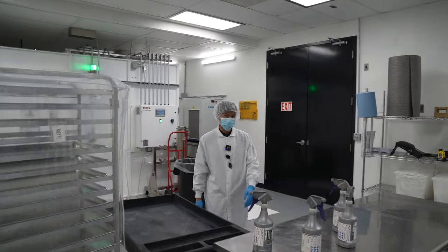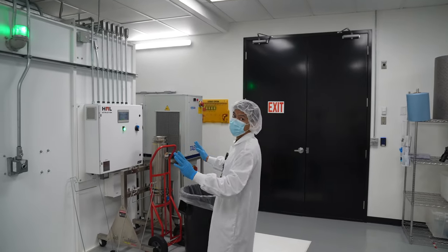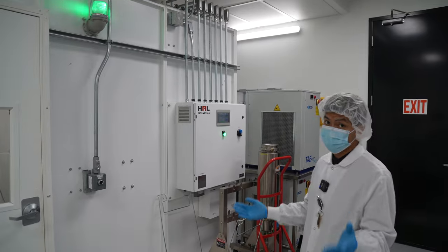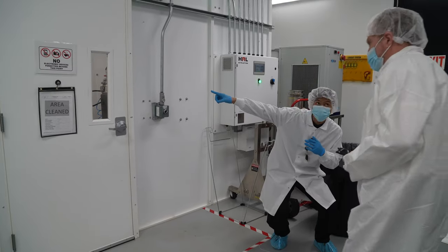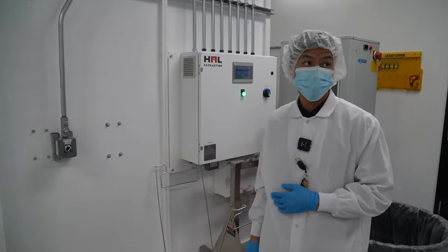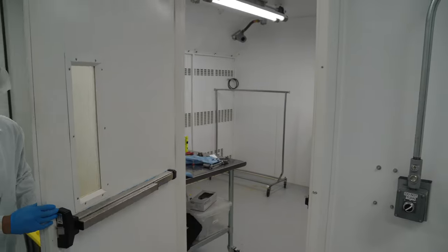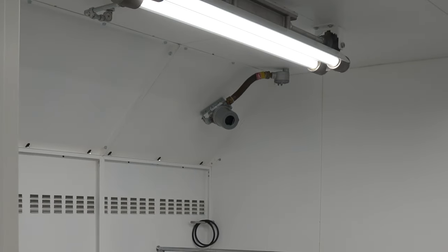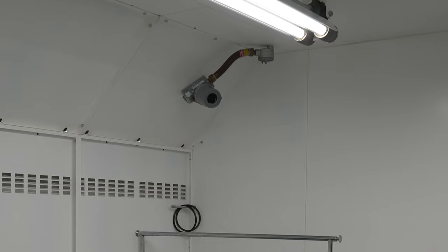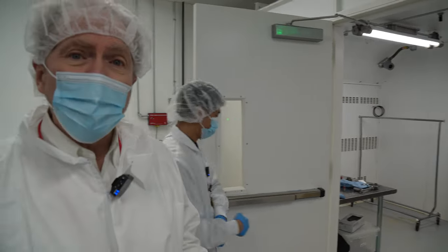I'd like to show you another camera system that's very difficult to install, and Bond was actually able to incorporate into our security system. Due to this being a C1D1 area, there are explosives stored in here. So to avoid any inadvertent explosions, we'll keep all the electronics behind this perimeter. There's a camera — that's a C1D1 camera, and not anyone can actually perform that installation. That's the explosion-proof camera. It does not mean that it doesn't get damaged in an explosion. It means it can be in an area that has high explosive gases and will not create an explosion. It is what we call an explosion-proof camera. And it's also tied into the Storm and Archive servers for full control of what's going on in this room.